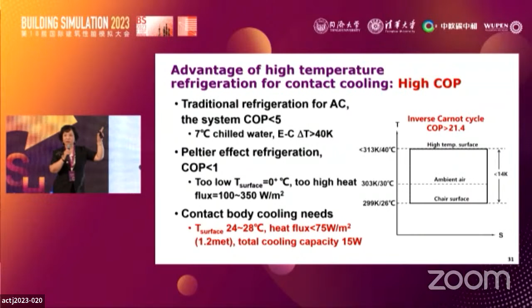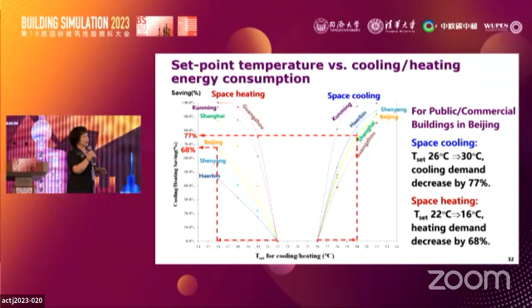Through the building simulation, we can get the cooling and heating energy consumption with the set point. We found that for public or commercial buildings in Beijing, if the indoor set temperature increases from 26 to 30 degrees, the cooling demand will decrease by 77%. If the heating set point decreases from 22 to 16 degrees, the heating demand decreases by 68%.